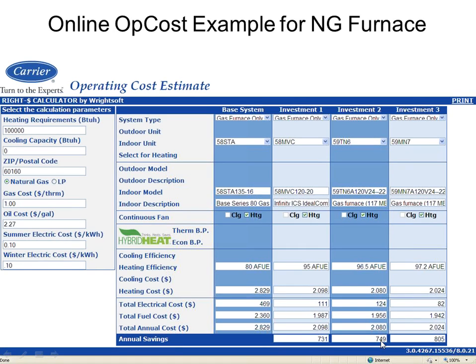It's basically saving an extra 10, 15 bucks or whatever. It's basically a wash as far as energy goes. Or I can give them this 59 MN7, which is the modulating gas furnace. He's a little bit more efficient at that particular size, which looks like a 120,000 BTU furnace. He's a 97% furnace. Oh, I should have picked that other one that was 98% to give him a better example, right? So he's going to save down here at the bottom $800 over this base furnace.